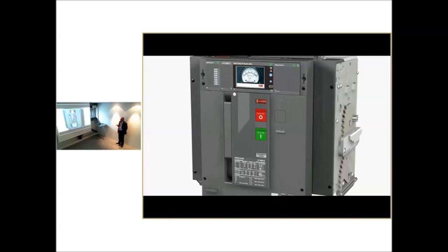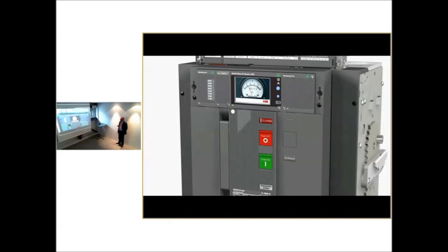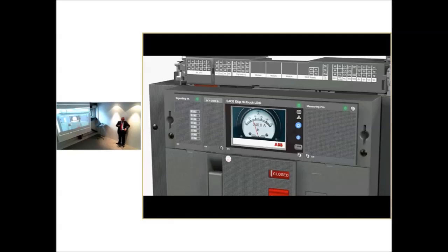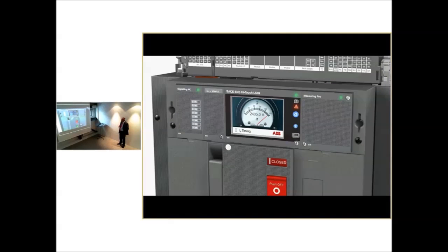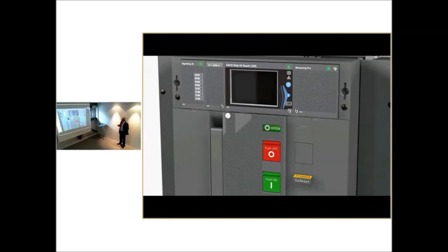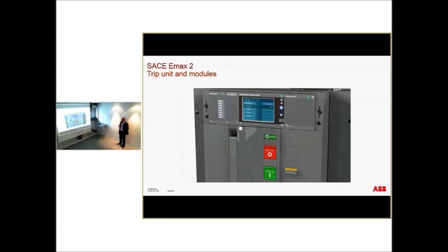Okay, you can have also the old design situation. You can decide how you want to see the current. The breaker trips and goes to alarm, you see here the trip indication. You push this button and you see what was the intervention. Okay, you got the L protection at 2012. This is the date and this is the current.